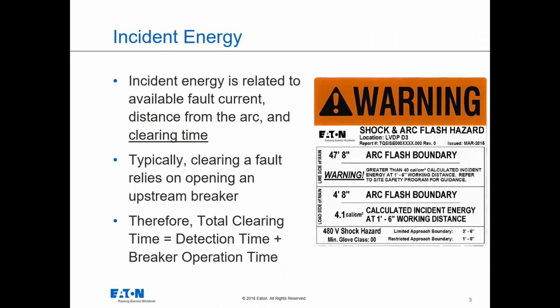safely. So that incident energy really only has three major points that go into the calculation: the available fault current, which is typically an upstream transformer source that's close to the equipment, or if it's a downstream branch piece of equipment, it's whatever the available fault current minus the cable impedance is coming down the wire, so to speak, to that equipment. The distance that the person is from the point of the arc or from the front plane of the equipment, and then the clearing time on the OCPD device, whether that's a fuse or a breaker.